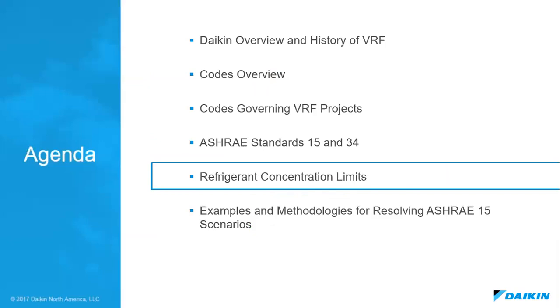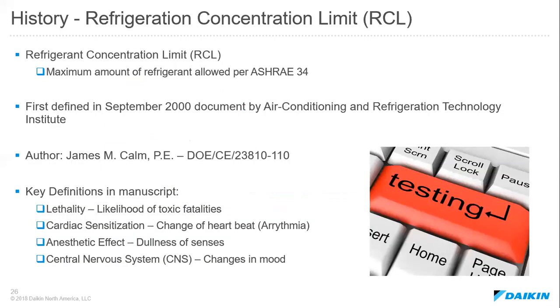Now I'll talk a little bit more in depth about refrigerant concentration limits. So the history of refrigerant concentration limits, or RCLs, like I said, RCL is actually called out in ASHRAE 34. Basically, an RCL, or refrigerant concentration limit, is the maximum amount of refrigerant that's allowed per ASHRAE 34. This came about in a document that was produced and published back in September of 2000. It was written by a gentleman by the name of James M. Calm. He's a PE based in Virginia. The document that he wrote is called DOE/CE/23810-110, which is a document that was published by the Air Conditioning and Refrigeration Technology Institute.